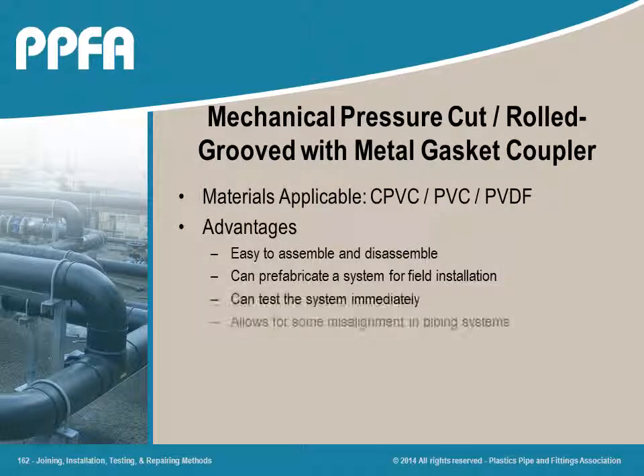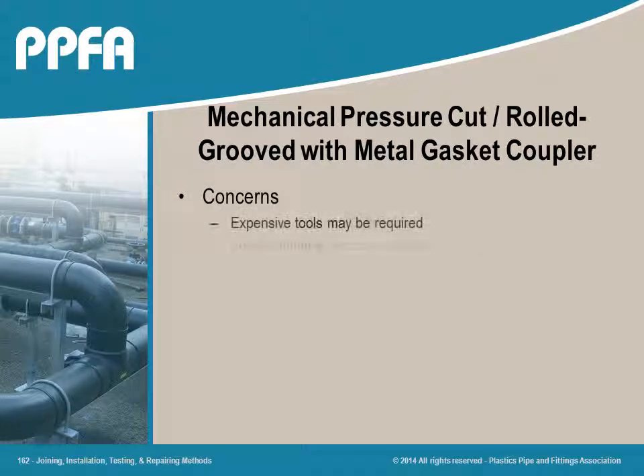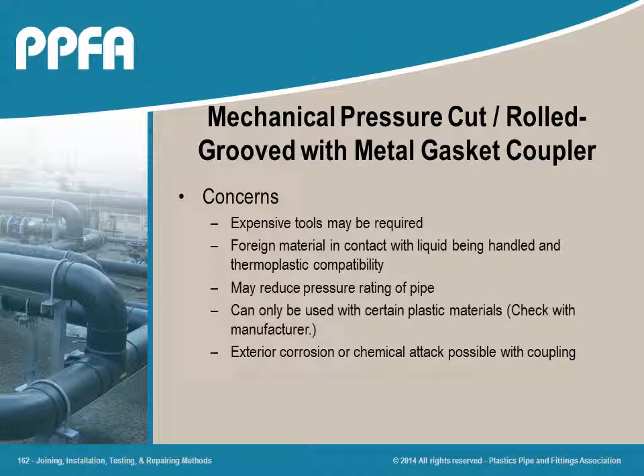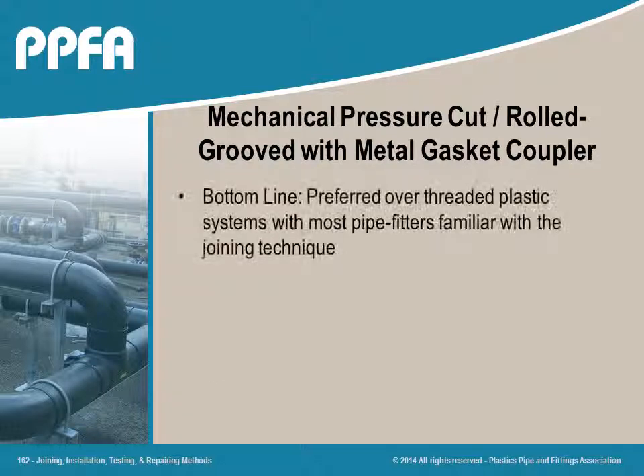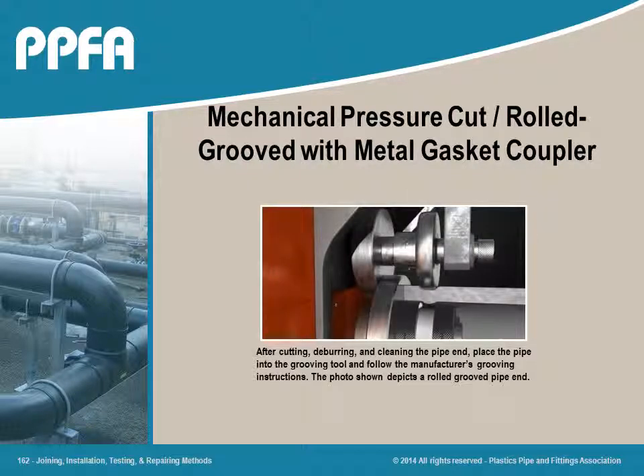Mechanically joined grooved-end piping systems can either have cut or rolled grooved pipe and an elastomeric gasketed metal coupler. The advantages are similar to flanging. That is, one can join or disjoin piping materials and prefabricate an entire piping system for shipping to the job site. Due to material characteristics, this system is recommended for vinyls and not for polyolefins.